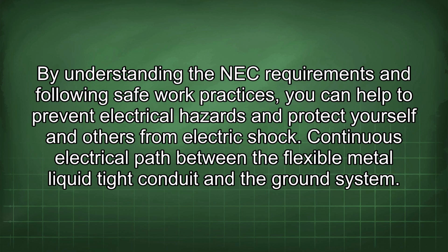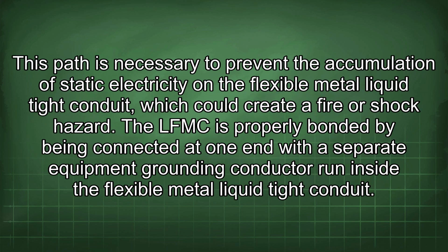Bonding provides a continuous electrical path between the flexible metal liquid tight conduit and the ground system. This path is necessary to prevent the accumulation of static electricity on the flexible metal liquid tight conduit, which could create a fire or shock hazard. The LFMC is properly bonded by being connected at one end with a separate equipment grounding conductor run inside the flexible metal liquid tight conduit.